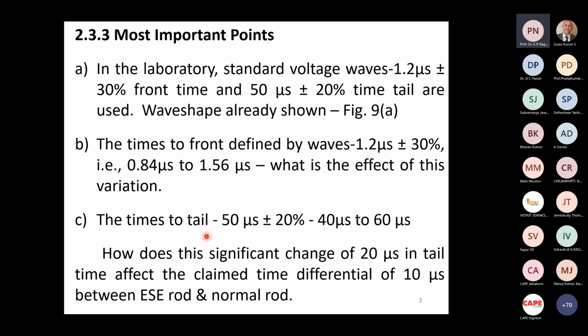Similarly, the time to tail has a tolerance of 20%, that means 40 microseconds to 60 microseconds. Now, we'll see just a little later. This is a standardized lightning impulse wave for tests essentially on power transformers. The real life lightning wave is far from this, very, very far from this, as we'll see presently.